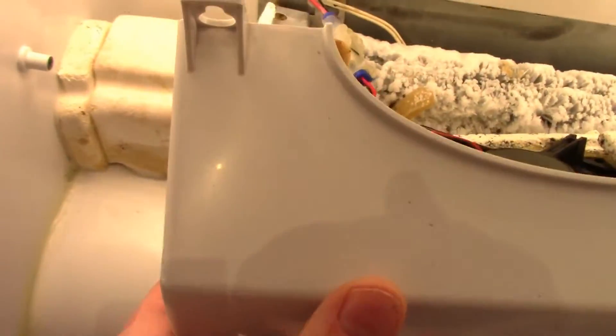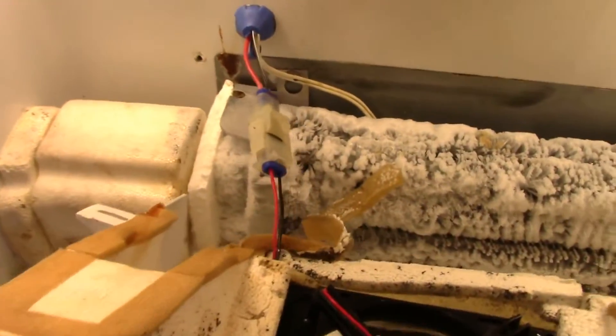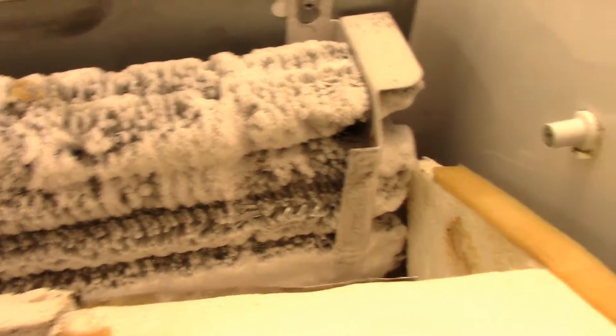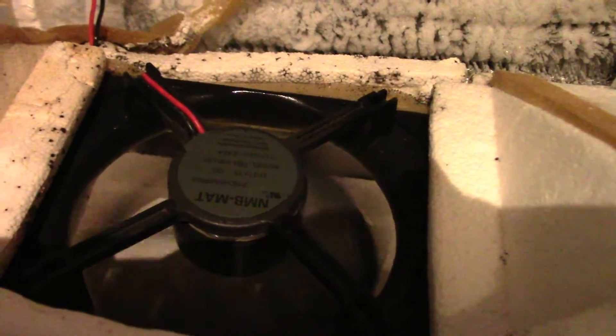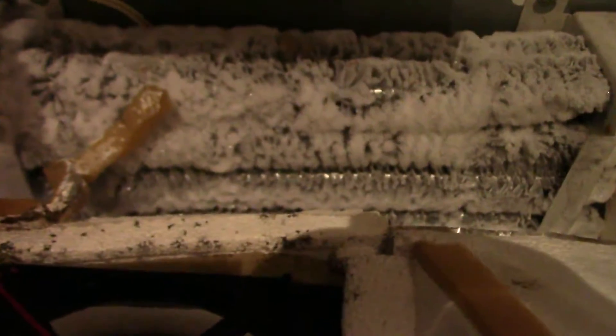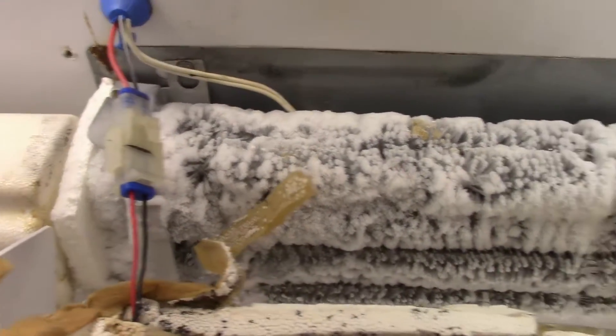So I'm going to have to get a hairdryer out to melt this. Okay, so I finally got it out, heat it up with a blow dryer. As you can see, just totally caked, and there's the fan that is pulling air across that evaporator and then up through the ductwork. I'm going to have to thaw this entire thing out to go any further.